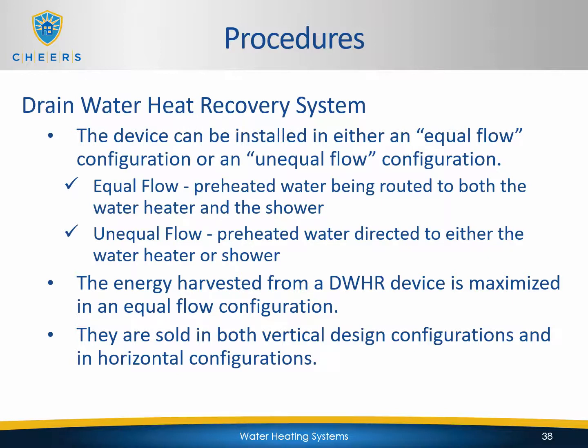The device can be installed in either an equal flow configuration or an unequal flow configuration. Equal flow means that the preheated water is routed to both the water heater and the shower. An unequal flow is where the preheated water is directed to either the water heater or the shower. So those are the two options that we have. The energy harvested from a DWHR device is maximized in an equal flow configuration. So we want that preheated water going to both the water heater as well as the shower. They are sold in both vertical and horizontal configurations.